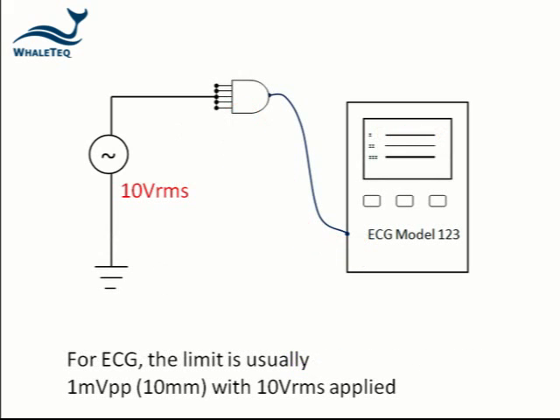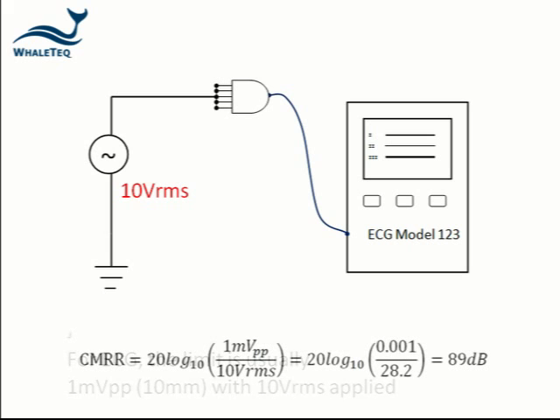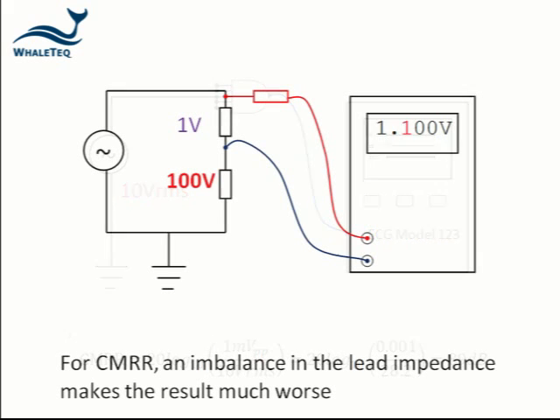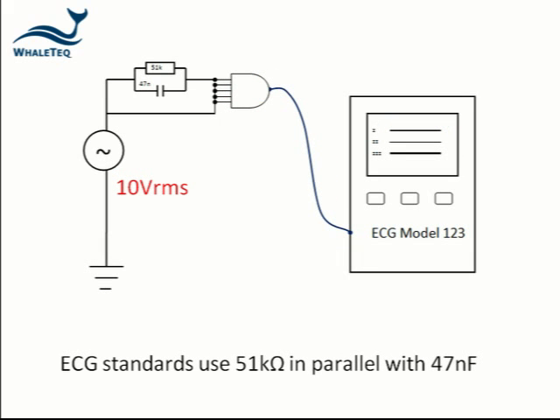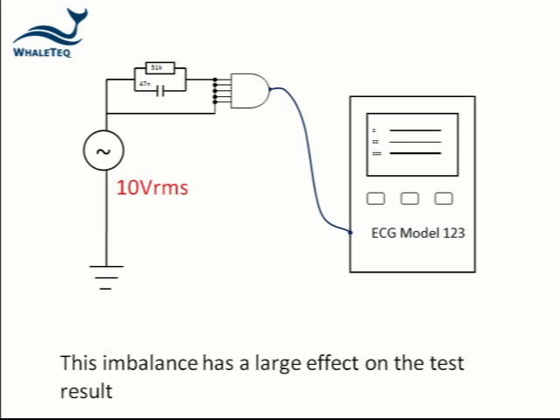In ECG standards the typical requirement is 1 millivolt peak-to-peak indication with 10 volts RMS applied. This calculates to around 89 dB CMRR. It turns out that for CMRR, an imbalance in the impedance in each lead makes the result much worse. Multimeters typically specify a one kilo-ohm imbalance. The ECG standards use a 51k resistor in parallel with 47 nF capacitance to represent connection to the body. This imbalance has a large effect on the test result.